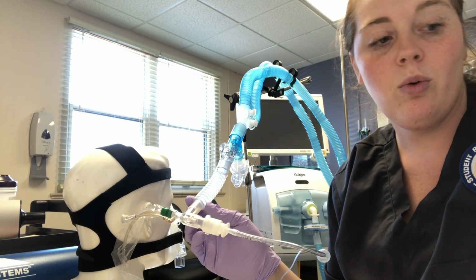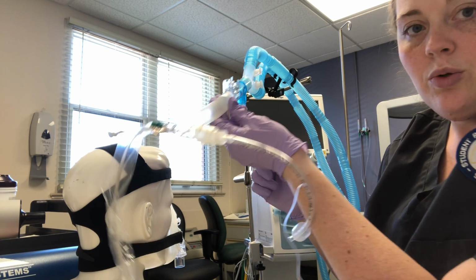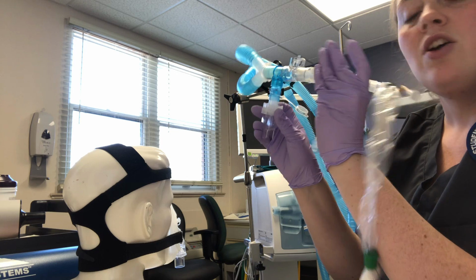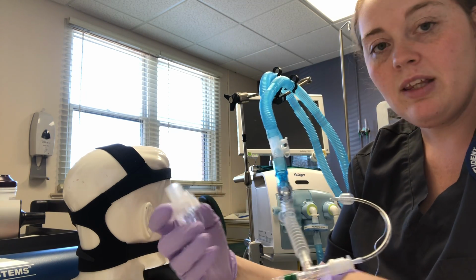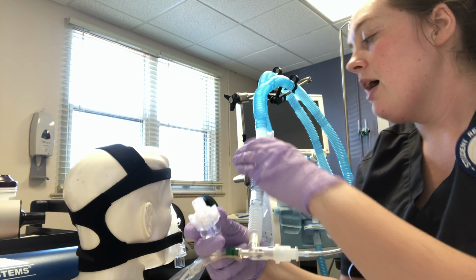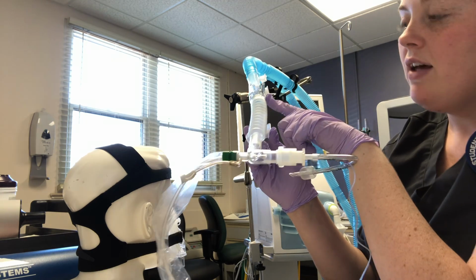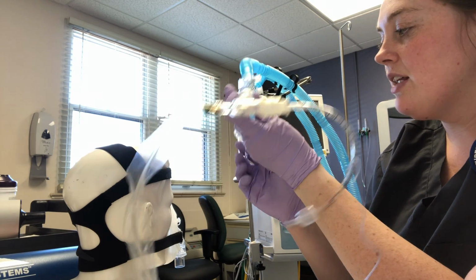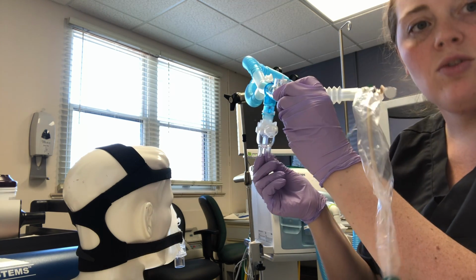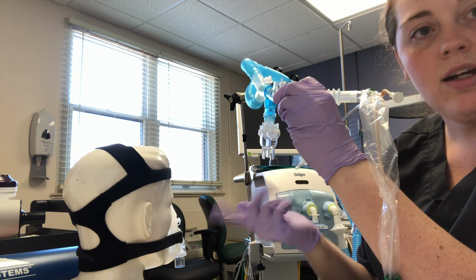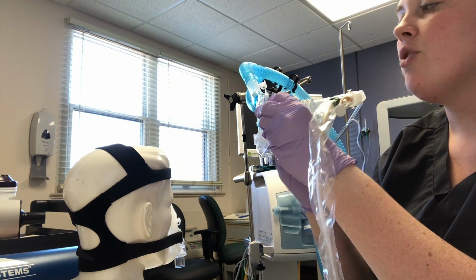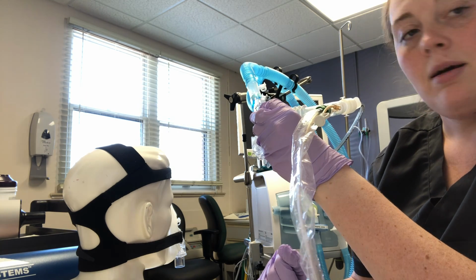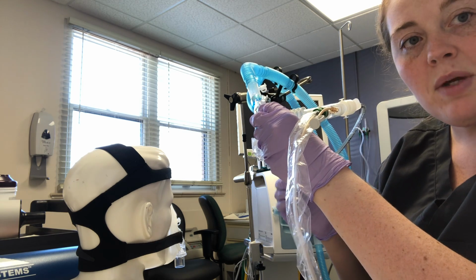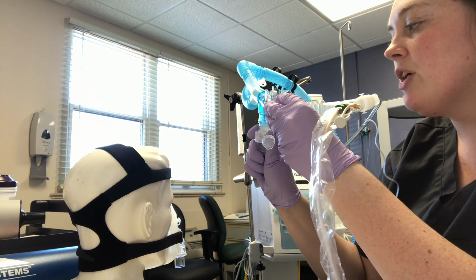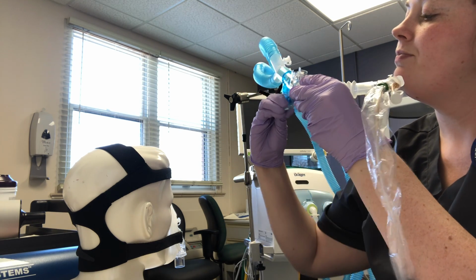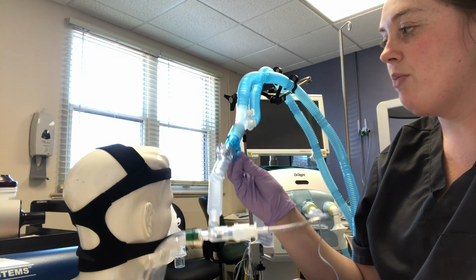So first of all, we'll just go ahead and do the SVN. So you go ahead and go like this, you can see. So you have your neb cup, and you go ahead and fill it with your medication that your patient will be using. And then, like I said, it just slides up into the T-piece where it opens up into the inside there, and that's how the patient's going to get the aerosol. So you're just going to attach, just like you do when you're doing a treatment, you can attach this to wall air, turn it on to 8 just like you would normally for your patient, and then your patient will get the medication from the SVN. Now, in order to help reduce dead space as much as possible, when we're done with the neb treatment, we can just remove the cup, and then we can cap it off. So that is how you do the SVN portion.